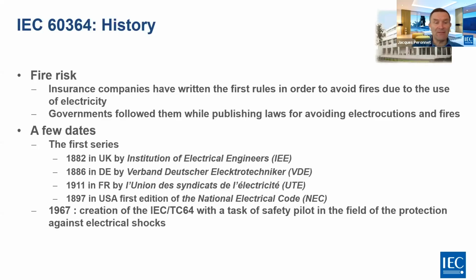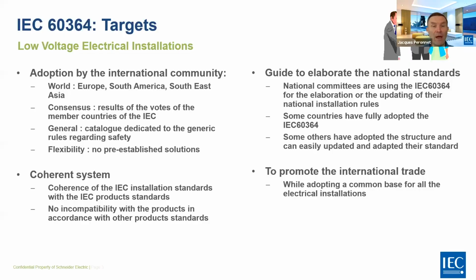In 1967, the IEC TC64 was created with the task of a safety pilot in the field of protection against electric shock. Regarding this IEC 60364, these standards have been adopted by the international community. So it's a standard which is used worldwide, in Europe, in South America, in Southeast Asia. The main exception is mainly North America, including Mexico, and also some countries in Asia and in South America.